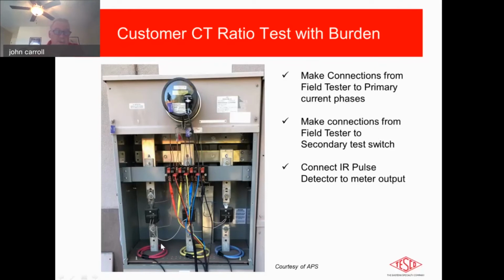So that's really what we're doing here. We're accurately measuring the current flowing through the CT. That's important because the CT is telling the meter it's one value. We're verifying that it is indeed that value. In this case, I had them double wrapped because a single wrap on these put the flex probe a little wider than I would have liked. And we have options to tell the instrument that it is wrapped twice because you're reading twice the amount of current.